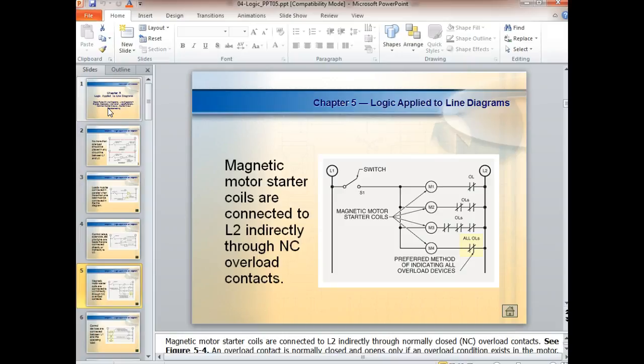So what happens with a motor? The motor draws a lot of current when it starts up. We call it starting current. Well, it's called rotor current. It's about 6 to 8 times, and it varies. Generically, if you don't know it, we assume that a motor will draw between 6 and 8 times its run current. So if I've got an overcurrent protection, what's it going to be rated at? Is it going to be rated at the motor's run current, or does it have to let the motor start? Got to let it start.